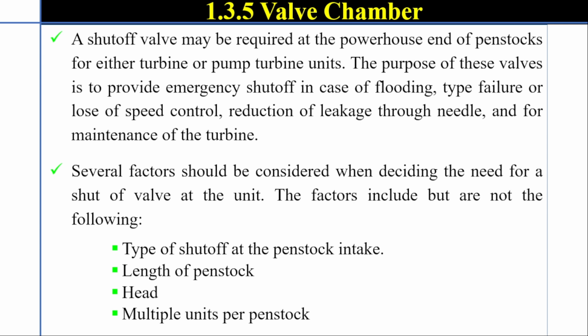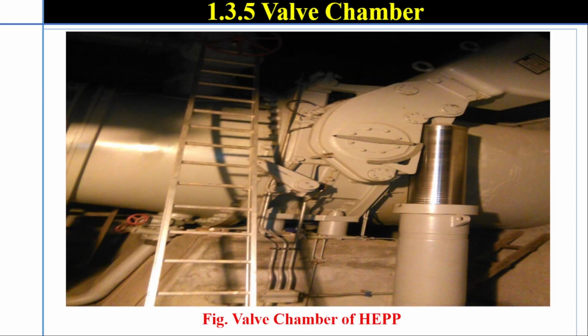Several factors should be considered when deciding the need for a shut-off valve at the unit. The factors include, but are not limited to, the following: type of shut-off at the penstock intake, length of penstock, head, and multiple units per penstock. This figure is the valve chamber of a hydroelectric power plant. As you can see, it has several valves.